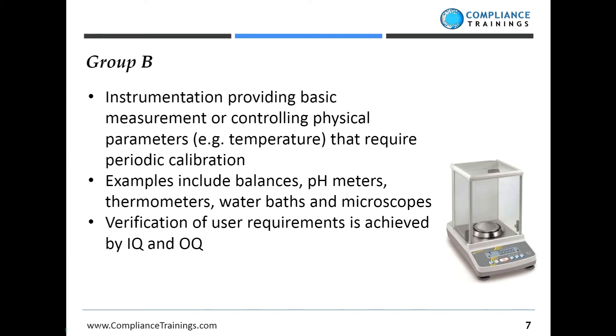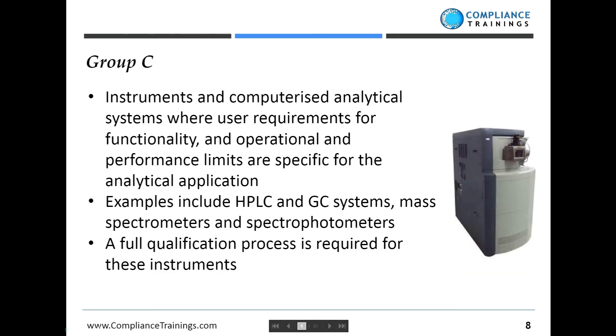Generally we recalibrate group B instruments regularly — pH meters are often calibrated at the time of use, and balances receive an annual calibration supported by daily check weights to make sure calibration hasn't drifted between times. Group C is the most complex type of instrumentation. These are instruments that generally have computerized data systems associated with them, including chromatographic systems, mass spectrometers, and spectrophotometers, and for these instruments we require a full qualification approach.